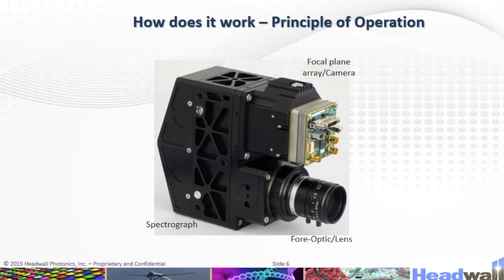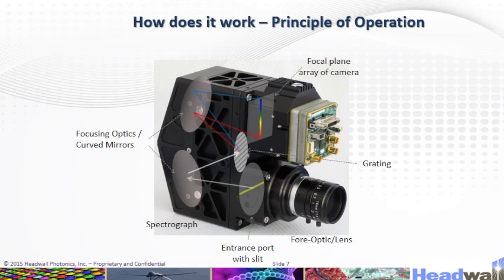This is a picture of a spectrograph, as you can see, with the fore-optic lens and the focal plane array camera on the top. Inside this spectrograph are optical components: slit, grating, curved mirrors, and focal plane array camera. With the fore-optics lens scanning the field of view, light goes in through the entrance port with slit, bounces off, and travels via curved mirror interface with grating to a second curved mirror, and then to the focal plane array.